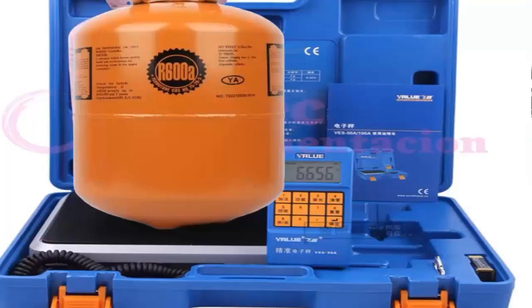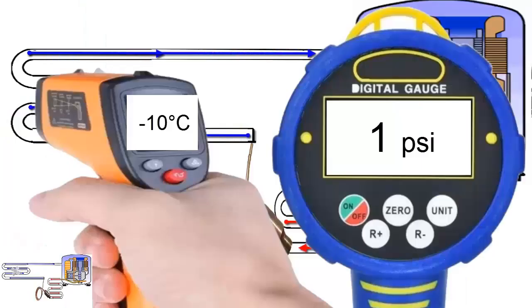For medium-temperature applications, the working pressure on the low-pressure gauge is 1 pound per square inch at minus 10 degrees Celsius.